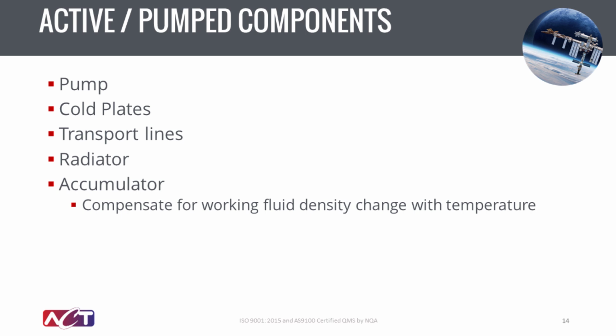So summarizing again the active components, this is very similar to any single phase pump system schematic you might see for terrestrial, but you'll have a pump, usually a space qualified pump with very robust qualification and acceptance test protocols. As I mentioned before, usually you'll have N+1, N+2 redundancy on that pump to make sure that you can absorb at least some failure mechanism.